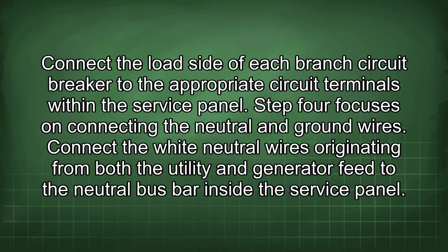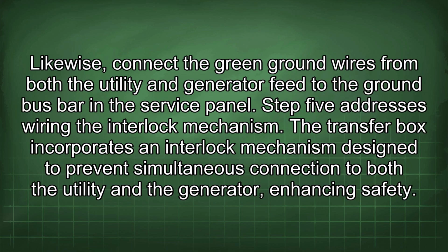Step 4 focuses on connecting the neutral and ground wires. Connect the white neutral wires originating from both the utility and generator feed to the neutral bus bar inside the service panel. Likewise, connect the green ground wires from both the utility and generator feed to the ground bus bar in the service panel.